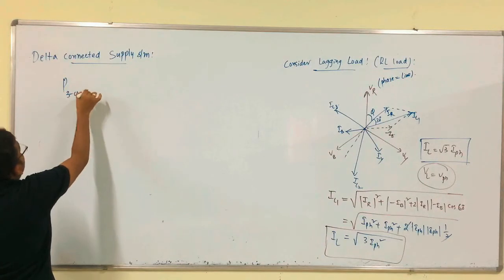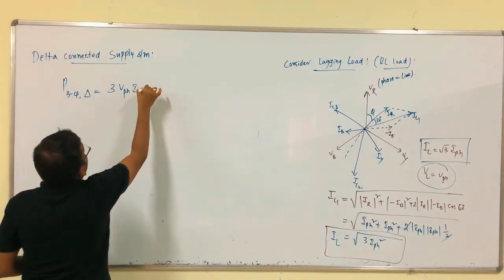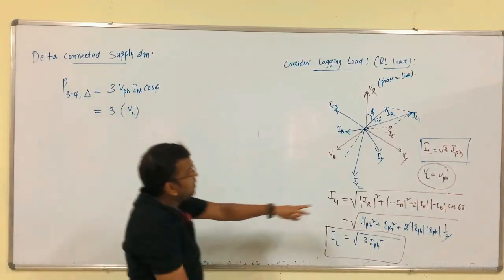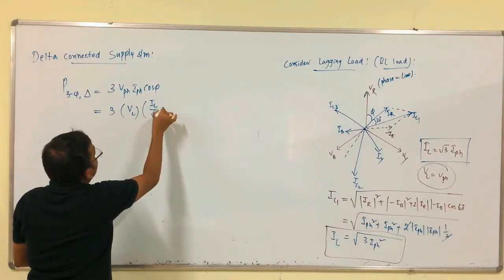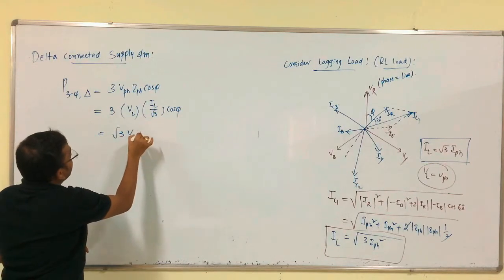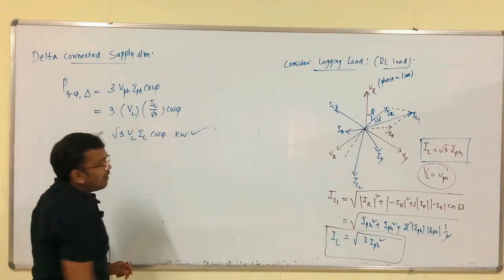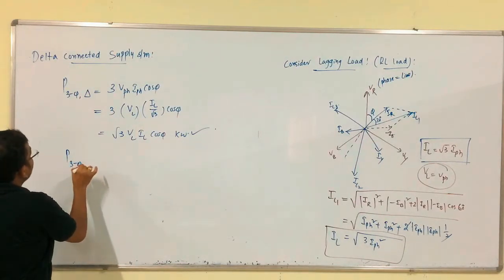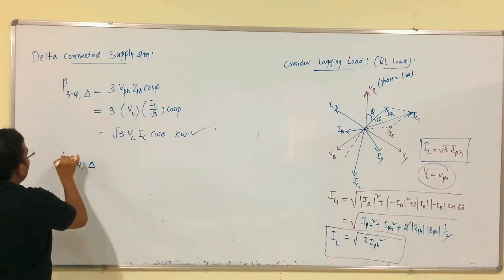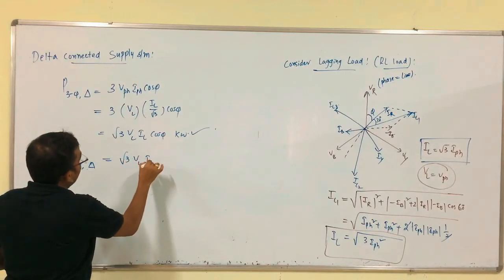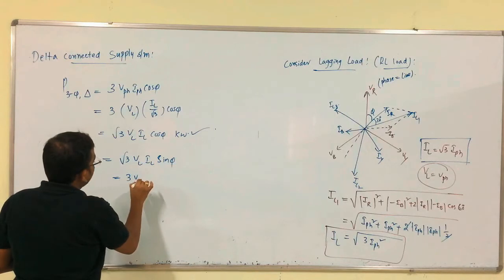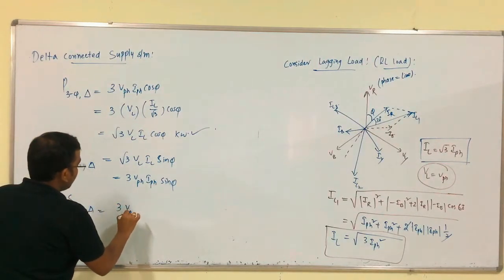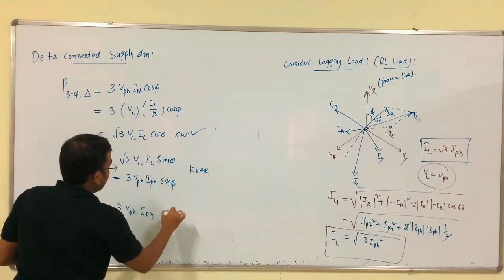Active power P = 3 × V_phase × I_phase × cosφ. Substituting V_phase = V_L and I_phase = I_L / √3, this gives P = √3 × V_L × I_L × cosφ (kilowatts). Reactive power Q = √3 × V_L × I_L × sinφ = 3 × V_phase × I_phase × sinφ (kVAR). Apparent power S = 3 × V_L × I_phase (kVA).